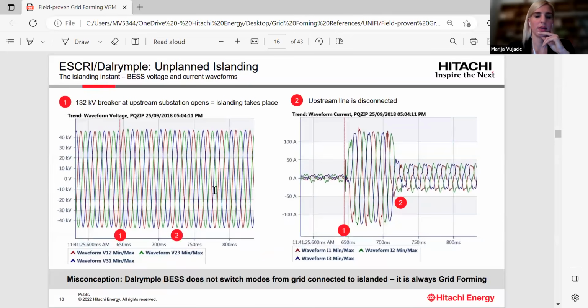So we can see the voltage and current waveform here. You can see that the robustness of the voltage waveform was demonstrated. No voltage shocks were experienced during this seamless transition. What we can see on the right side is that BESS was running unloaded at the moment when the upstream breaker opened. This is the current that was supplied by the battery energy storage system and drawn by this 132 kV line. And at the moment when the protection system disconnected the line, the current was then defined by the load. This is how the seamless transition was demonstrated.